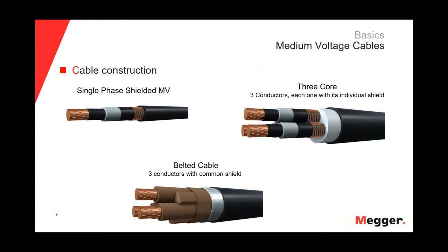Besides the single-phase cable, we can have other constructions. For instance, we can have the three-core cable in which we have three conductors, each one with its individual shield or concentric. And then we have the belted cable in which we have three conductors with a common shield. We can have different constructions for medium voltage cables and that will affect how we connect our test equipment to do the VLF test or the tan delta test.